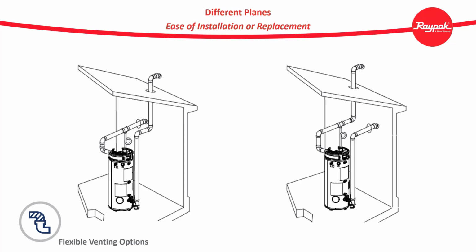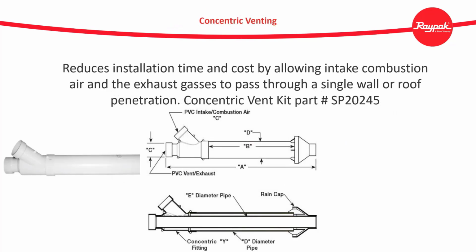The Triton allows for venting on different planes. The air intake and the vent termination can be on separate faces of the building. The drawing on the left here shows the intake through the wall with the exhaust through the ceiling. In the right drawing, it is the opposite. Concentric venting is also possible with the concentric venting parts kit. With concentric venting, you only need one hole in the building.